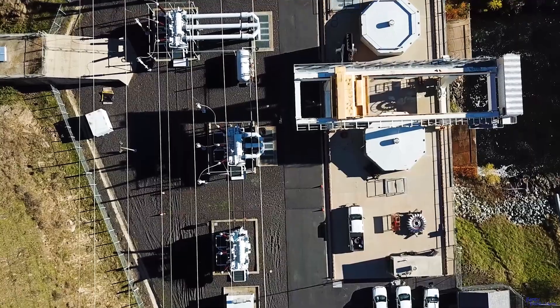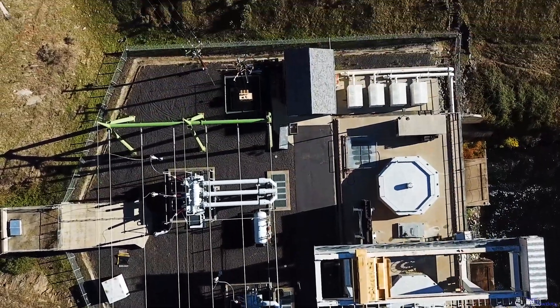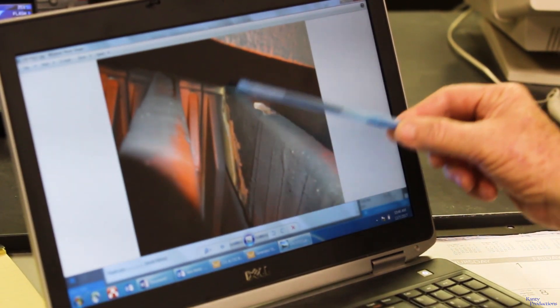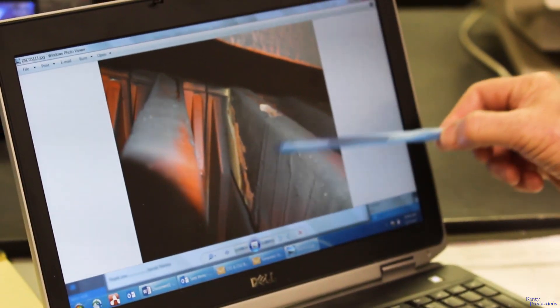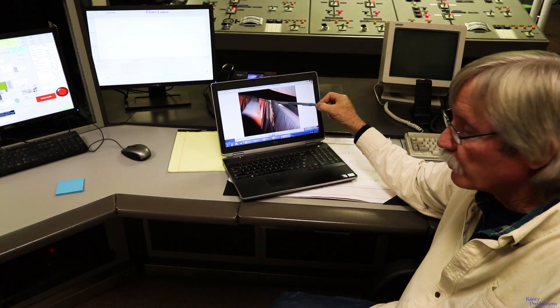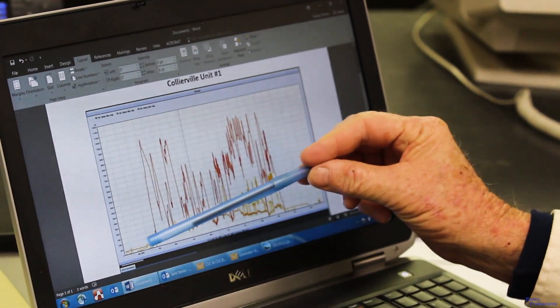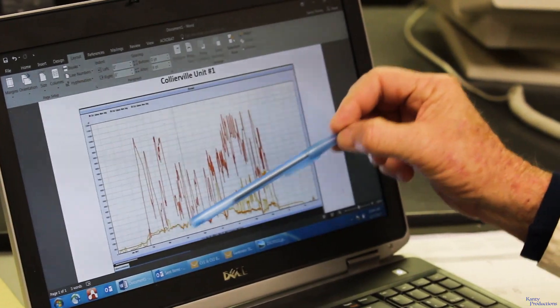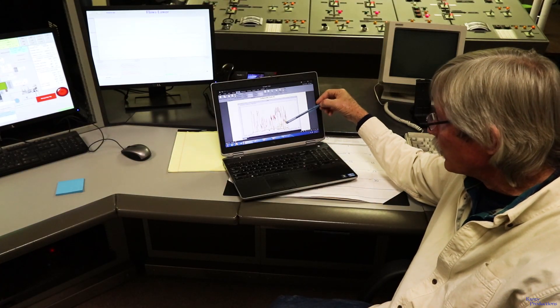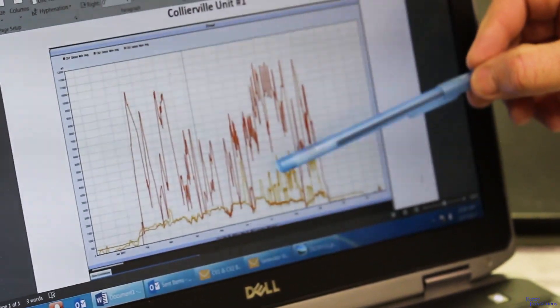The things that keep me up at night are equipment failures. This is a burn spot on a generator stator winding — a Roebel bar. This is a partial discharge burn area. We have to repair this before we have a failure. If we take a look at the partial discharge screen, we were running the units hot and loaded, and you can see the partial discharge here in orange start to increase.